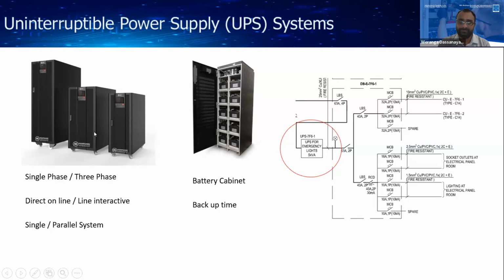So when you are going to extend an electrical distribution system, you have to clearly explain these kinds of things: what are the components available in this system, and whether UPSs are installed in this system. Also, backup time is very important because with time, the batteries are degrading. So you have to ensure whether all UPSs are running with their full backup time when you are doing a condition audit.